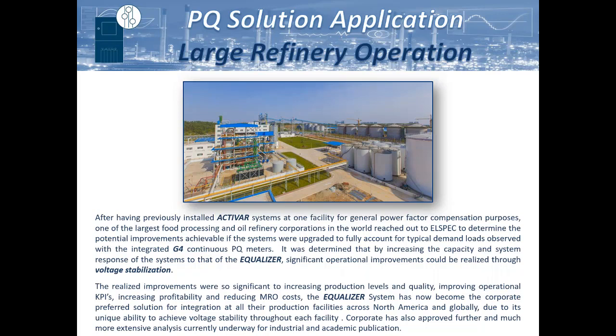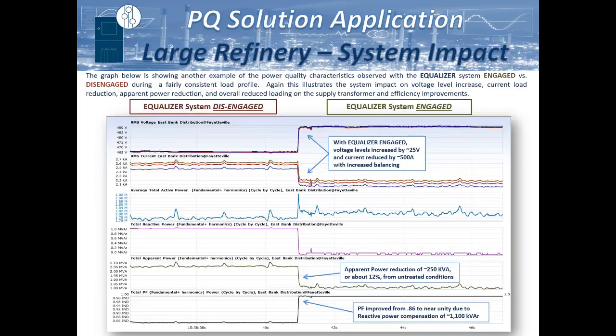So we got that approved, which is another benefit of our systems: you can add additional capacity or modify how they function, versus traditional systems where what you have is what you got, right? Once we increased the capacity and the response time up to an Equalizer, you can see the marked difference. They were running about 467 or so on their voltage. As soon as we turned on the system, it went straight up to about 498, or 489, I'm sorry. And you can see the significant impact on the current.